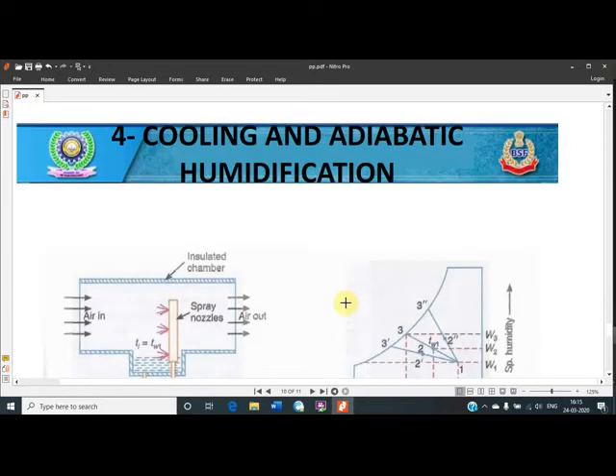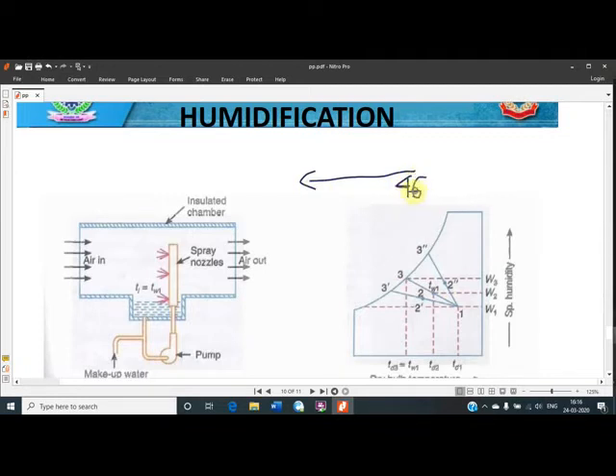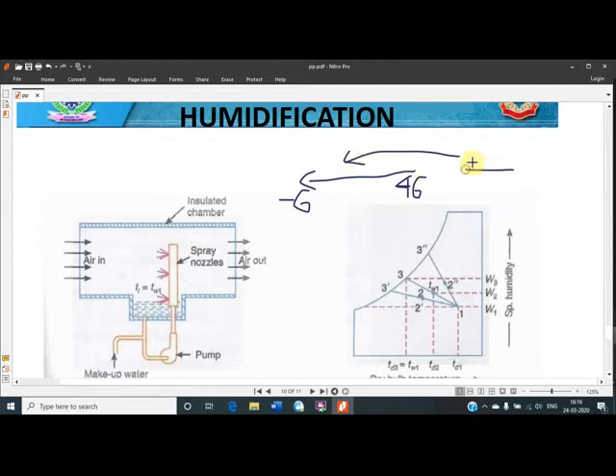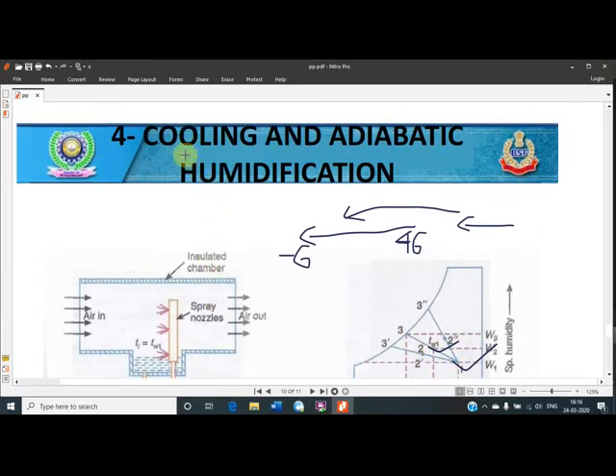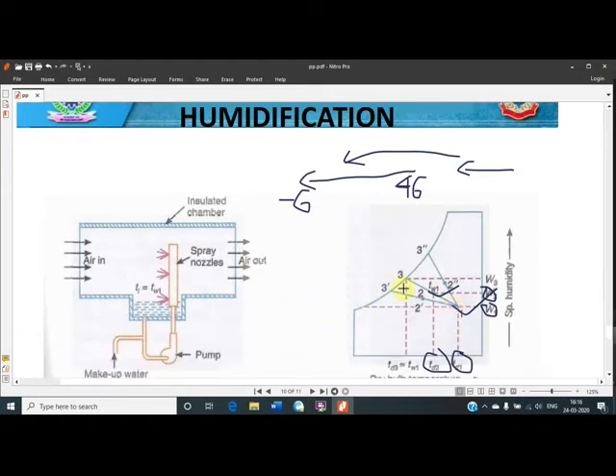The next process is cooling and adiabatic humidification — meaning we are cooling, but instead of dehumidification, we are humidifying, increasing the humidity. For cooling, you move from higher temperature toward lower temperature on the psychrometric chart. At the initial point, the temperature was higher, and at the second point the exit temperature is lower, so they have cooled. But additionally, they are humidifying — the humidity was less initially and now humidity is more. The term 'adiabatic' is used because when we move along the wet bulb temperature line or enthalpy line, no heat exchange takes place.